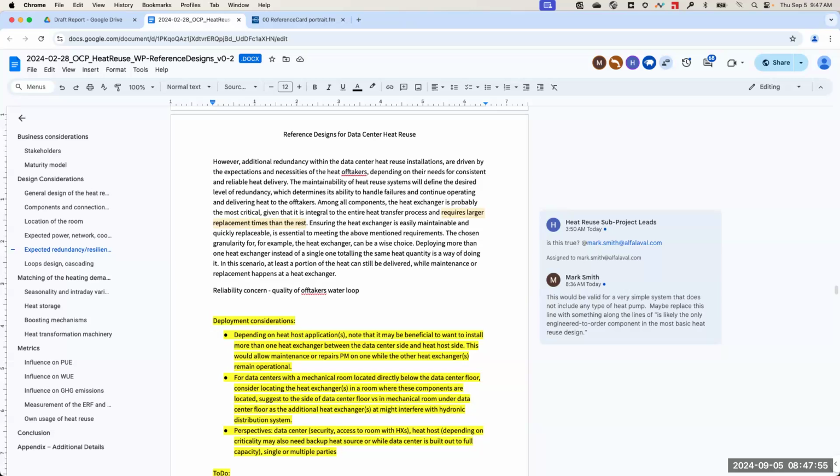So basically, you have to specify that the off-taker has to make sure he's meeting certain requirements on the quality of his water and on the materials of construction, so you don't get galvanic corrosion or whatever. Exactly, because the heat exchanger is an interface and it will probably belong to both of them, or maybe to one of them, but you have to take into account what's happening on the outside. Yeah, some of that responsibility also falls on the off-taker.